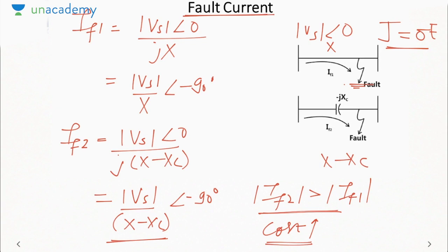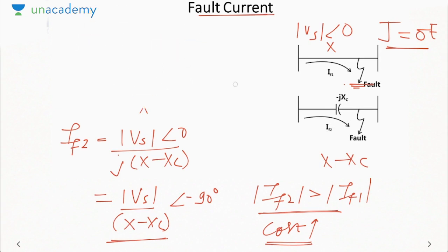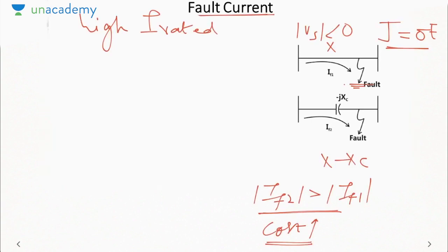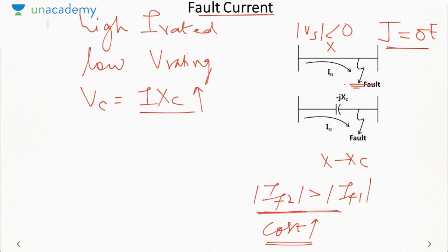Now usually what happens is this series capacitor, since it is connected in series with the load, will have a high current rating. But it must have a low voltage drop, so a low voltage rating. But in case the fault current increases, the voltage of the capacitor, which is I into Xc, will also increase. Due to this high voltage, the capacitor may get damaged. So we need to find a way to reduce the voltage across the capacitor.